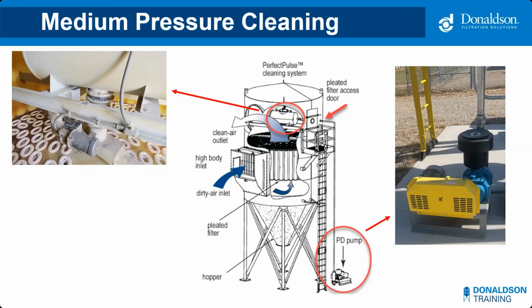The other item circled there is that reservoir tank I mentioned just a little bit ago. It's located just above the arm assembly that will spin around a central motor there, and the bags are laid out in a specific arrangement to ensure the pulse is directly down the length of the bag to allow for the most effective cleaning and no wasted air.